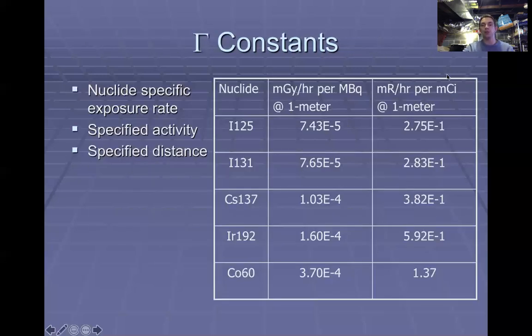But it's important to know that actual dose rate coming off the source. You need to know the activity of the source, and you need to know the distance. That will allow you to calculate expected dose rates at various positions of a source, which is essentially what you're doing when you're designing shielding. You know a certain activity source is going to be used in a certain location. You have an idea of the isotope. So then you have to decide, okay, how much shielding do we need in the walls? And that's really the whole process. But there's a lot of details in that simple 1, 2, 3 step.